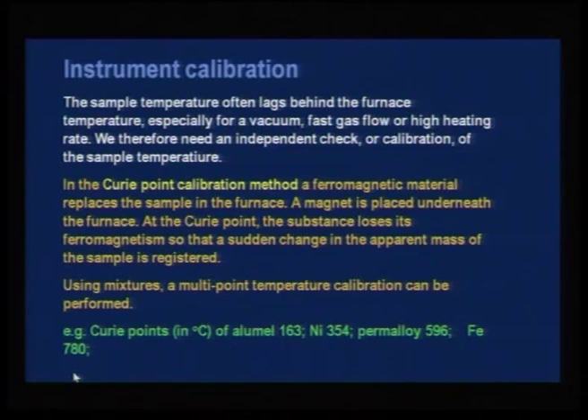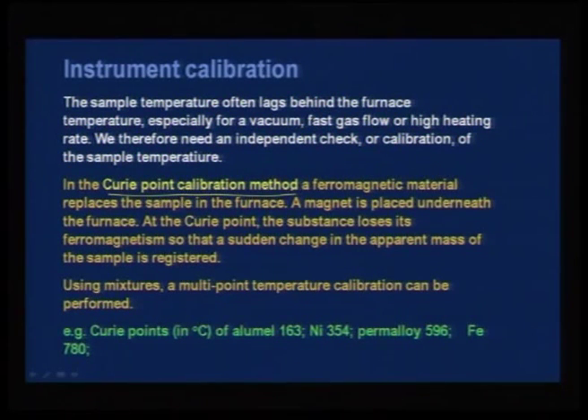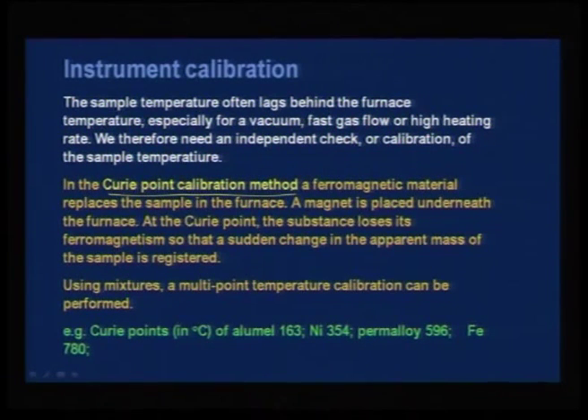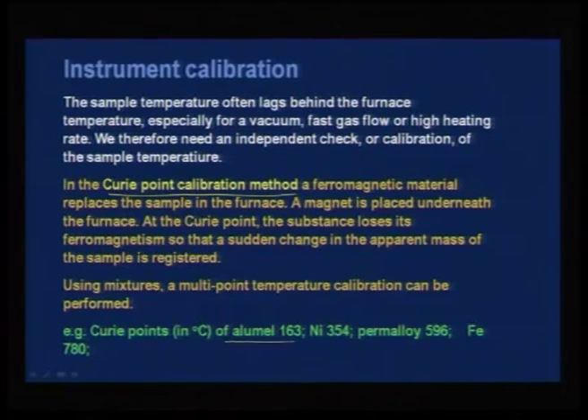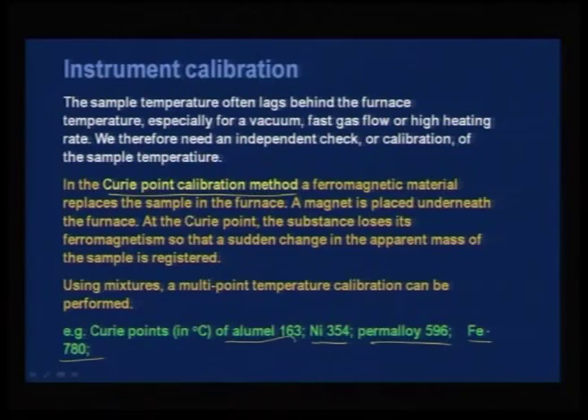TGA involves instrument calibration — weight calibration and temperature calibration are both needed. Today many instruments allow zeroing and adjusting error for temperature. Several standards are available, like alumel, nickel, permalloy, and iron — all having Curie points at specific temperatures — which can be used for internal calibration.